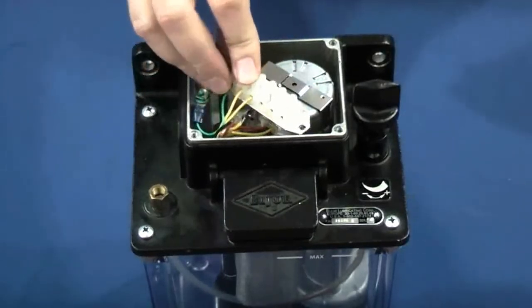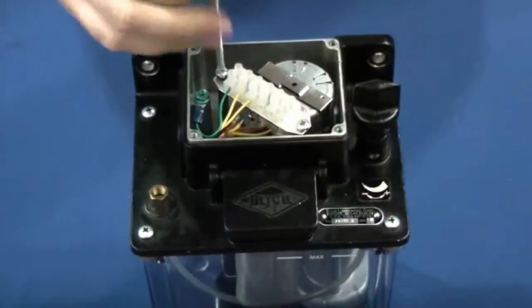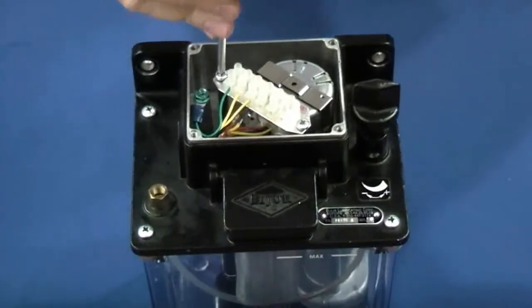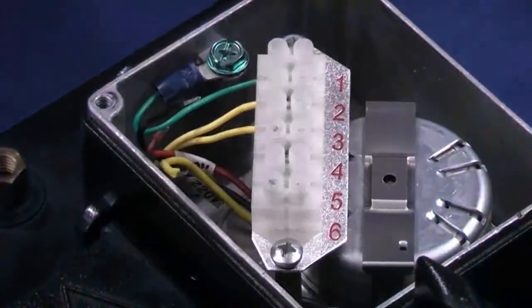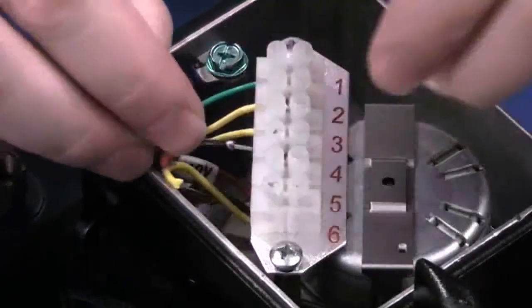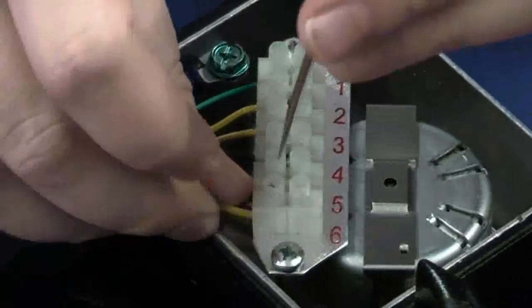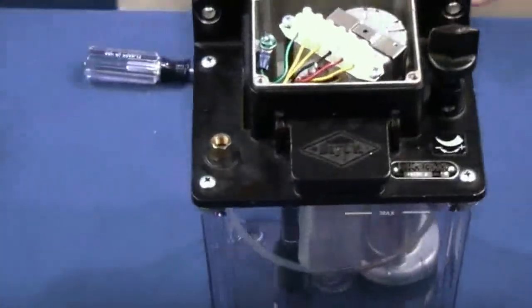Next, we will connect the terminal strip back to the standoffs on the unit by inserting the screws. Next, we will replace each wire back into the terminal strip. We will start with the black wire into number four, followed by the red wire into number five, and the yellow into number six. And last, we will just replace the motor cover and the four screws.